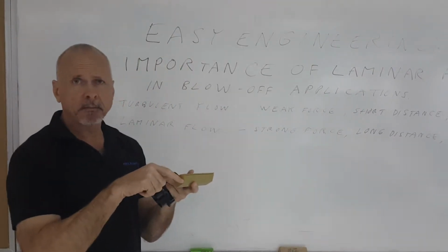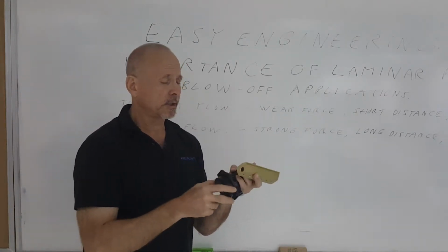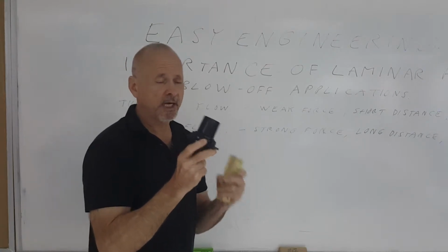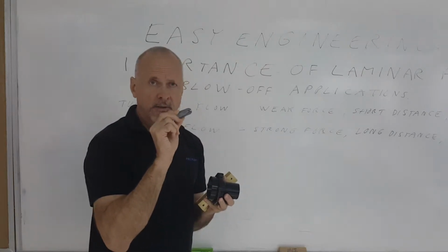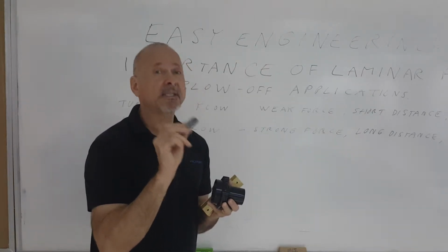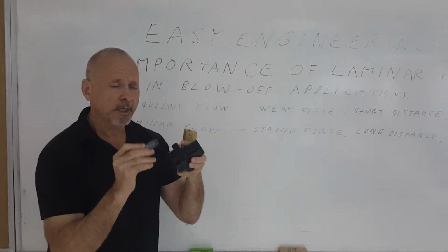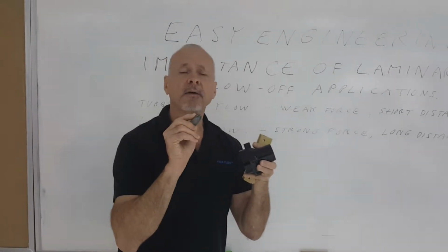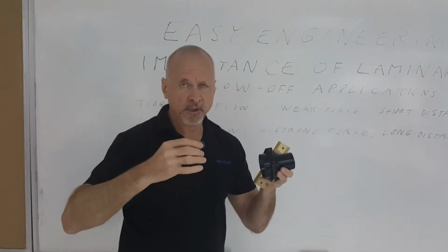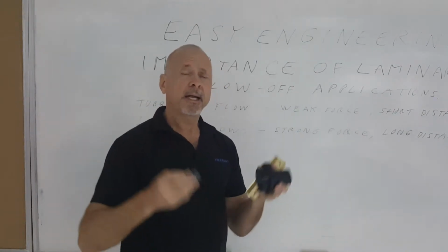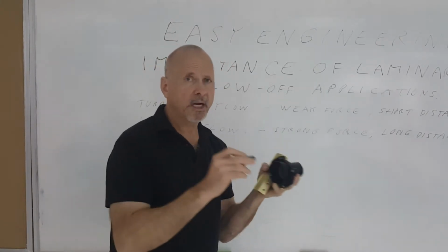You have a small gap, which is maintained by a shim in the air knife situation. You have a small gap in the air amplifier with a shim inside as well, to maintain that gap. With the nozzle, you have various holes that are of a specific size to let the compressed air out. But in every single situation, the compressed air is coming out and going off a particular type of surface, which actually draws in air from the surrounding atmosphere. And that air is combined with the exiting compressed air, and it converts it into a much higher flow.